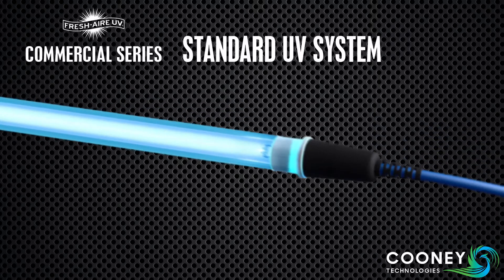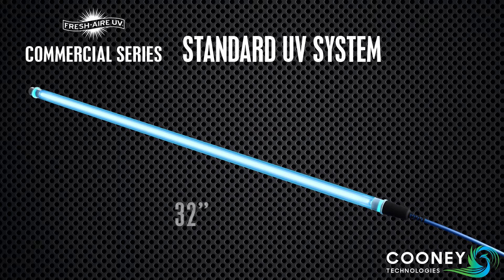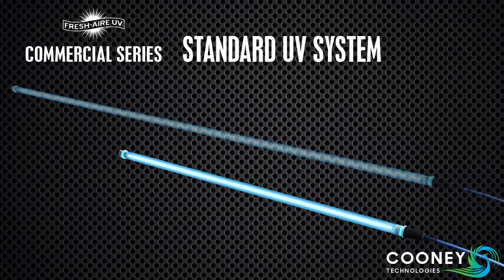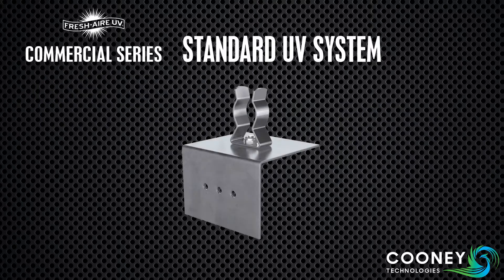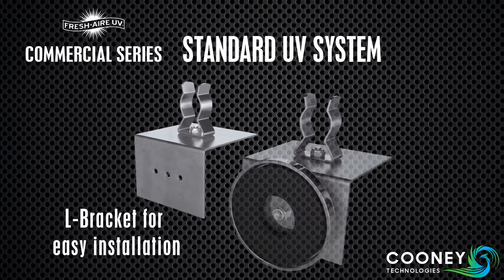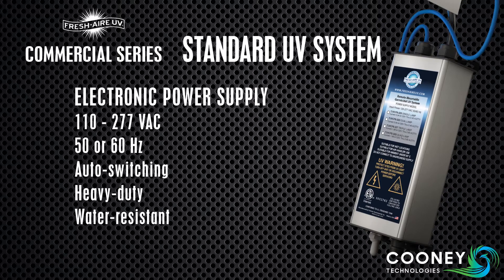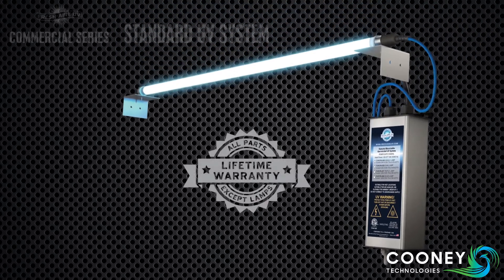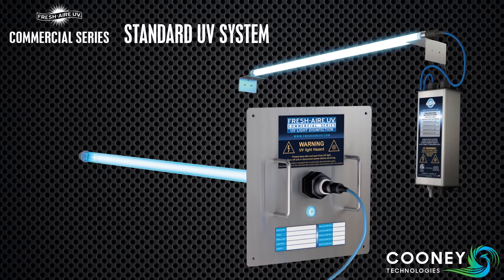Our standard commercial systems feature one- or two-year Fresh-Aire UV hard quartz UVC lamps, available in 32 or 60-inch lengths. For airborne disinfection applications, 32-inch high-output lamps are recommended. This system comes with L-brackets for easy installation, and optional mounting magnets for even simpler installation onto metal surfaces. The systems are powered by our 110 to 277-volt, 50 or 60-hertz, auto-switching electronic power supply. This heavy-duty ballast comes in a water-resistant NEMA enclosure with a lifetime unlimited warranty. The standard commercial system is also available in an externally mounted panel mount configuration.